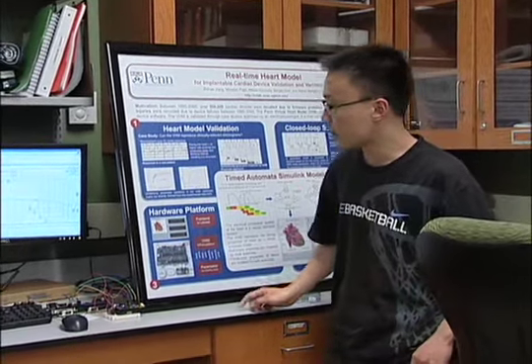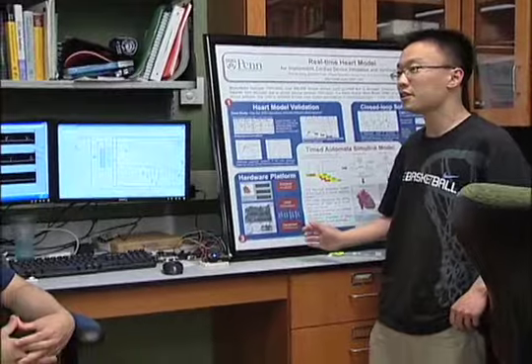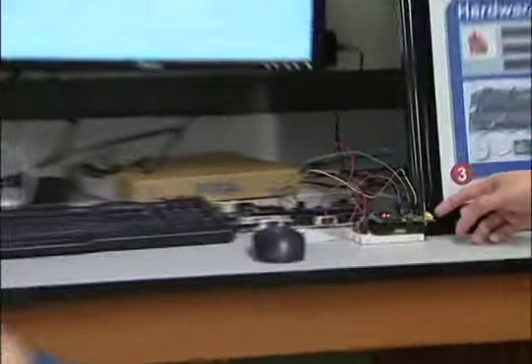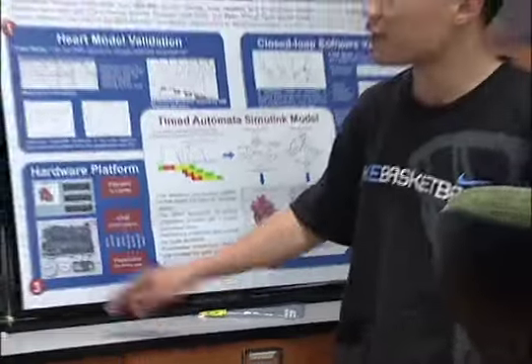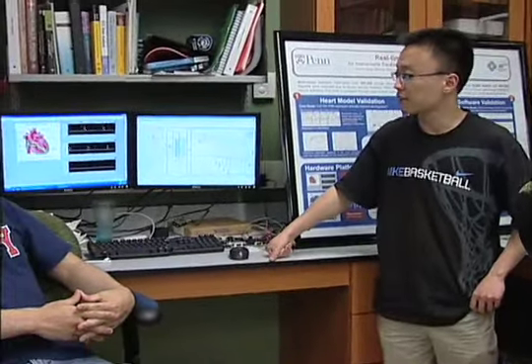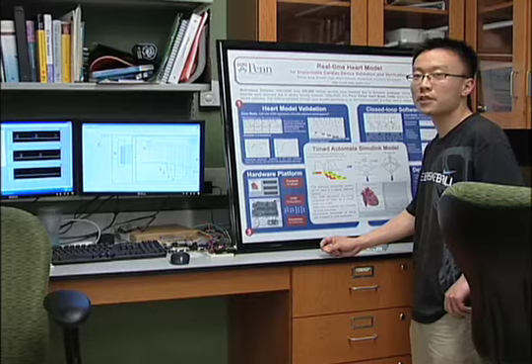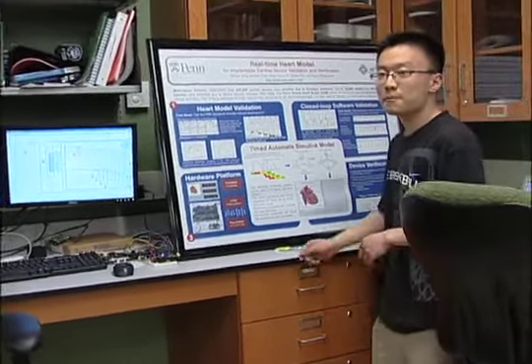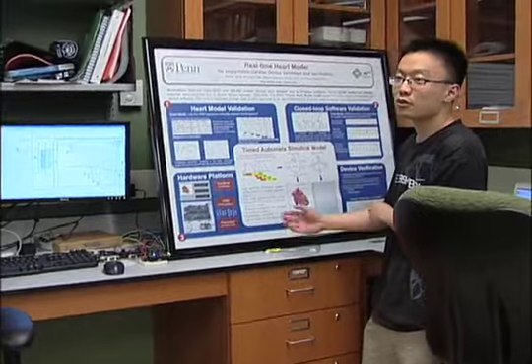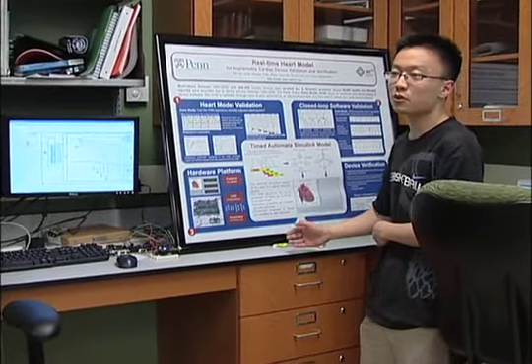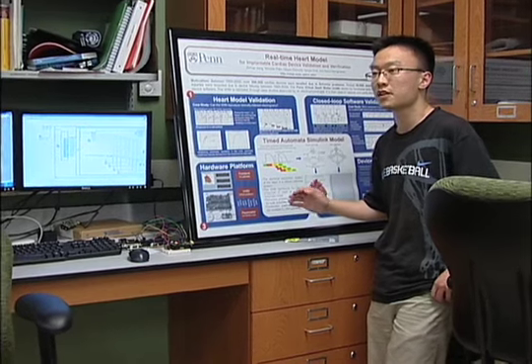It's very important to test these devices in a closed-loop manner. We developed a heart model by simulating the electrical conduction system of the heart using timed automata. We implement our heart model on hardware which has FPGA, and we can validate the pacemaker functions in a closed-loop manner and do formal verification.